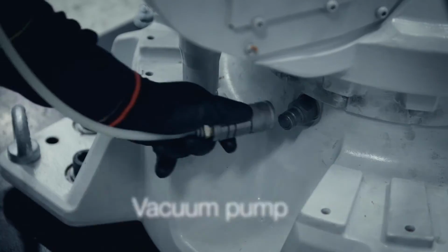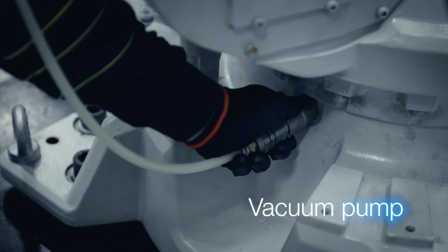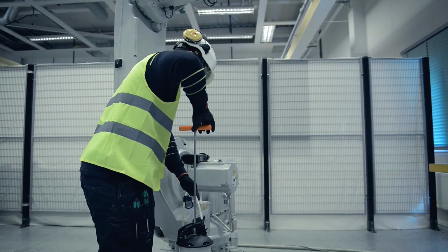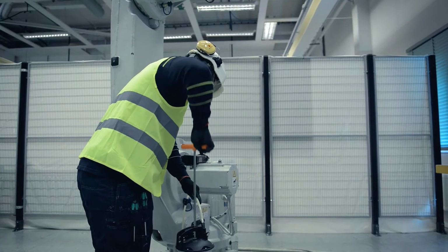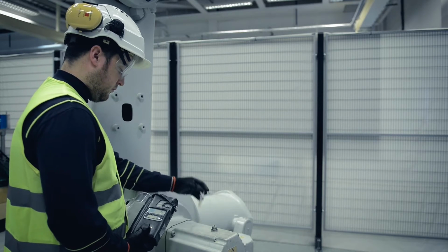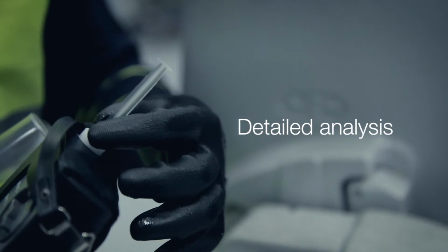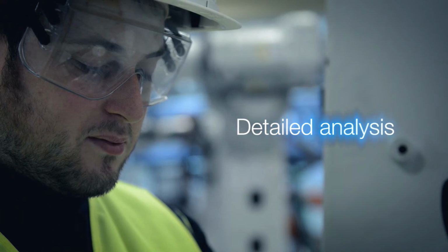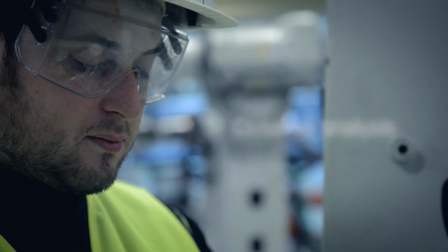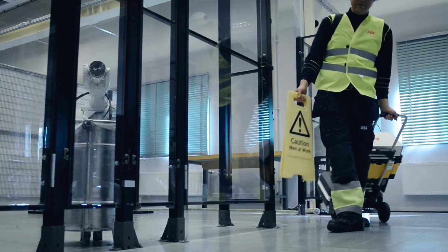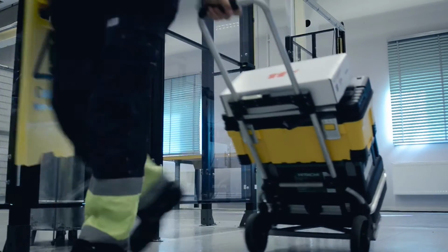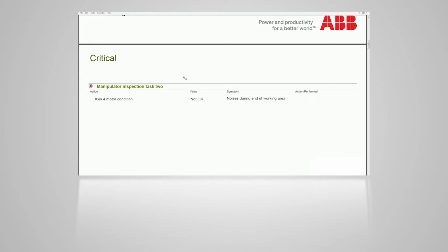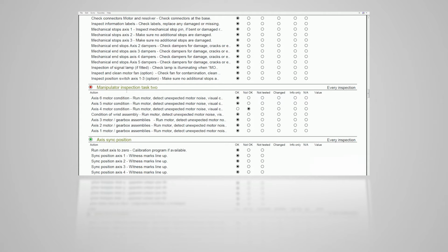If any oil changes are to be carried out, then a vacuum pump is used to remove the oil, saving both time and the inconvenience of waiting for the oil to drain. If the oil reading is at a critical level, then we recommend further investigations, such as a more detailed analysis, as this may indicate that the gearbox is badly worn and close to failure. After the inspection is complete, any critical indications are suitably shown in orange and red on the inspection document and brought to your attention, where a follow-up action plan can be discussed and agreed.